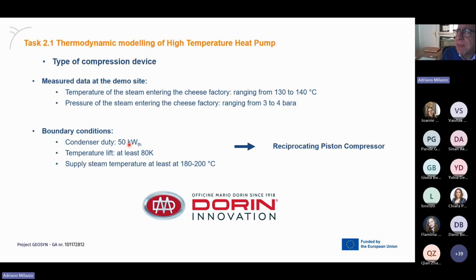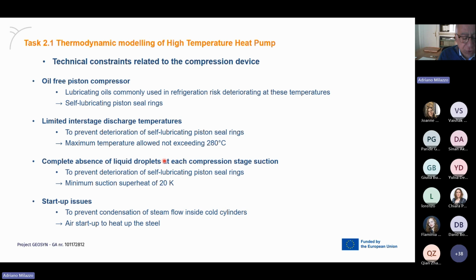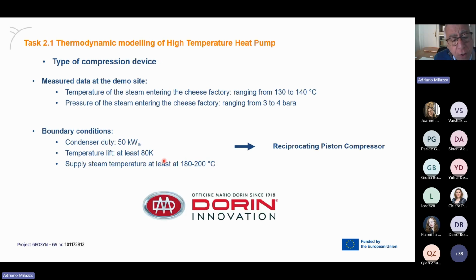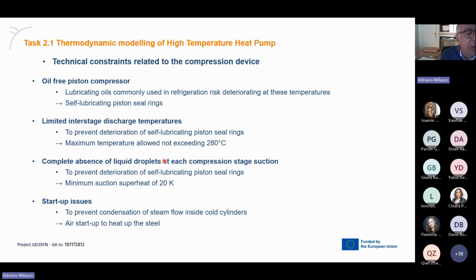But in our view, it's quite interesting because there could be a market for small scale heat pumps with quite high temperatures, 180, 200 degrees, and cooling power around, as we say, 50 kilowatts. The temperature lift is an important concept. It is the increase in temperature between the low temperature source and the high temperature sink in which we want to send the heating power.